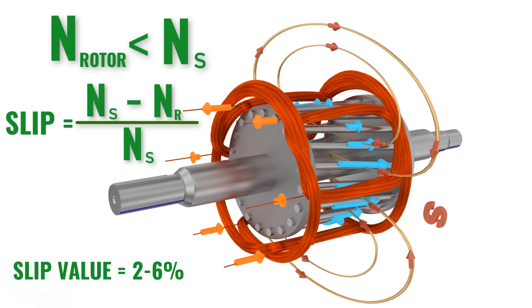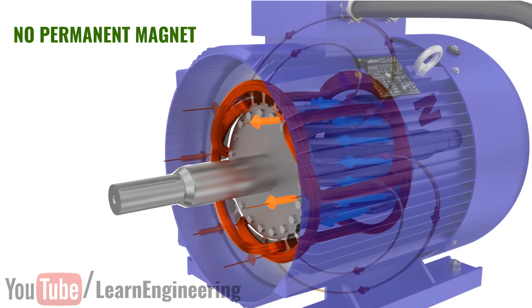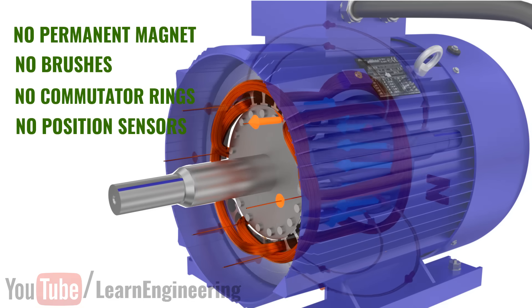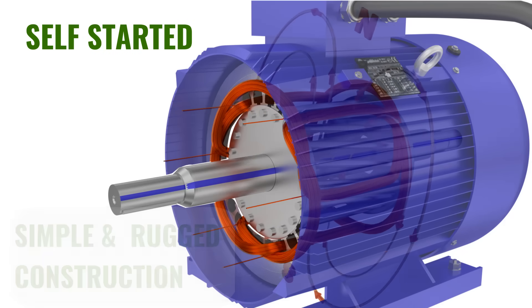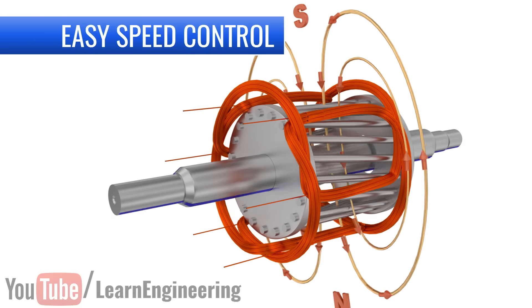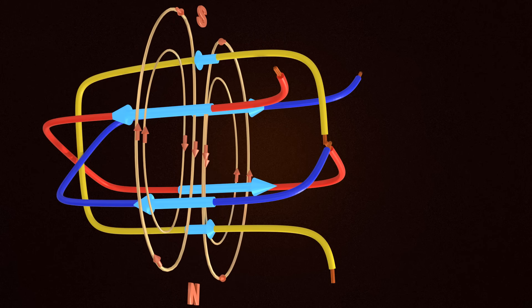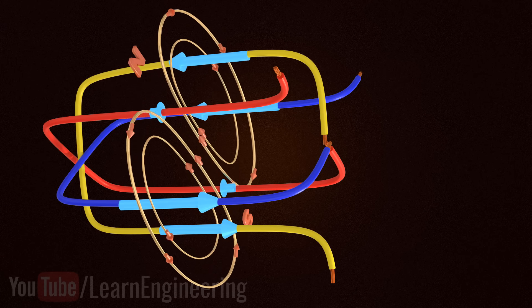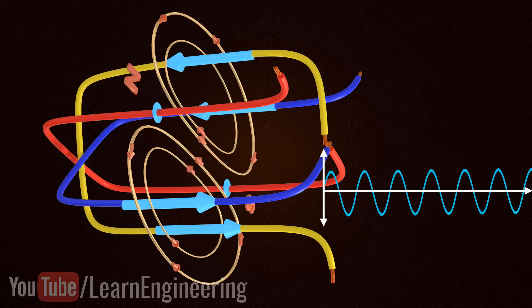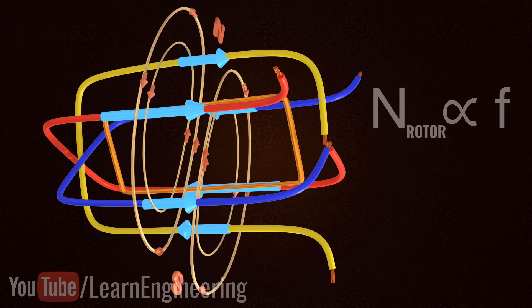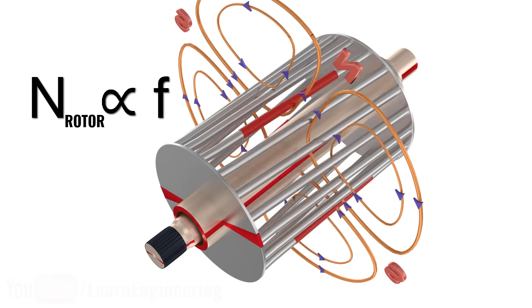Now let's understand why induction motors rule both the industrial and domestic worlds. Induction motors do not require a permanent magnet. They do not even have brushes, commutator rings, or position sensors like other electrical machine counterparts. Induction motors are also self-starting. Most importantly, induction motor speed can be controlled easily by controlling the input power frequency. The speed of the RMF is proportional to the frequency of the input power, and because the rotor always tries to catch up with the RMF, rotor speed is also proportional to AC power frequency. Thus, by using a variable frequency drive, one can control the speed of the induction motor very easily.